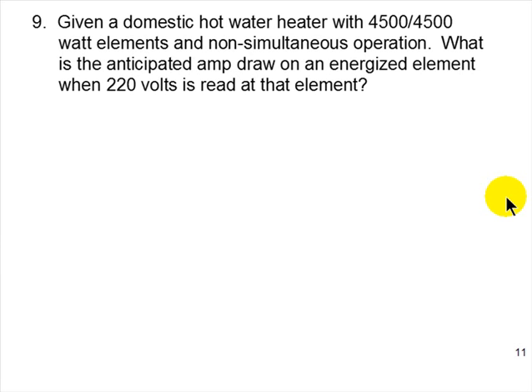9. Given a domestic hot water heater with a 4500 over 4500 watt element and non-simultaneous operation, this is as common as it comes. The electric element for a hot water heater is almost always going to be 4500 over 4500 non-simultaneous, meaning both of those 4500 watt elements are not going to run at the same time. You can wire any heater for simultaneous operation, but you better have the breaker and the wire size you need to do all that.